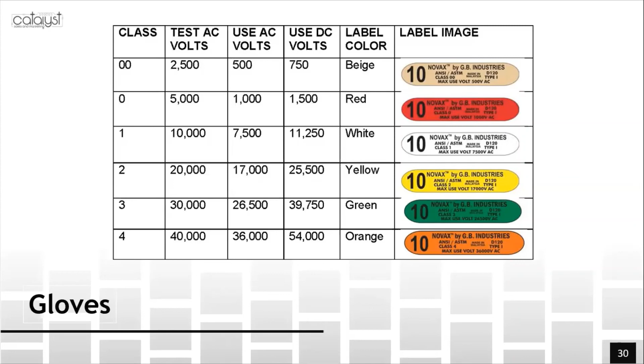When you have to get your gloves tested, CSA recommends getting your gloves tested every 6 months. When you send them back, no matter whose gloves they are or wherever you send them, here's what they're looking for: cracks, pinholes, cuts, and abrasions, as well as the thickness and ozone damage.